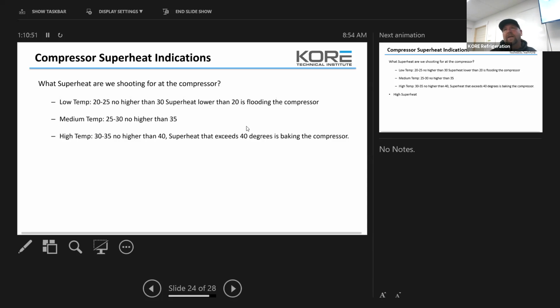Oh yeah, anytime, because what the temp's telling us is how the valve's feeding. When you get down to temp, if your valve's adjusted correctly, that's how it's throttling back and forth. It's hard to take a superheat reading otherwise, because the TXV, as it modulates, is going to allow more liquid through or throttle back, and that's going to change how it's affecting your compressor. Plus, if the coil is warm, the superheat is going to be higher because it's picking up a lot more heat while it's trying to get down to cooling pressure. So it's flooding that coil really hard.